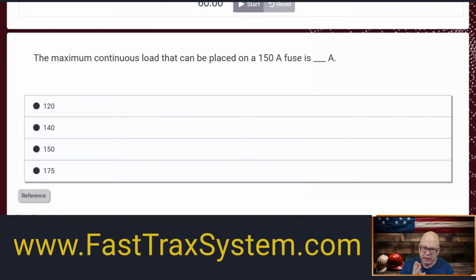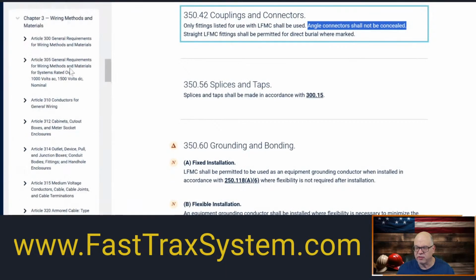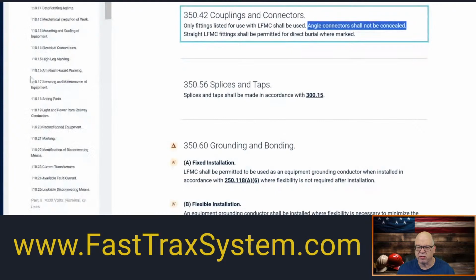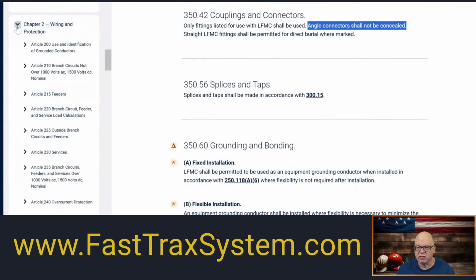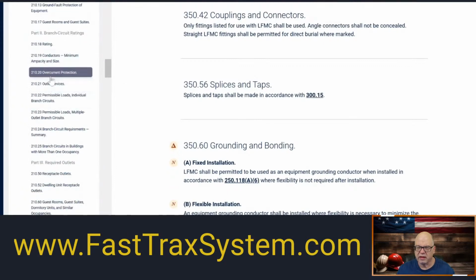So first things first, continuous. The device is rated for 150 amps, and nothing was stated, so it's a fuse. With continuous loads, you're limited to 80%, which is the reciprocal of 125%. So the first thing we want to see is, what is the maximum continuous load that can be placed on this 150? All right, well, let's go to the NEC real quick. Since we're still talking about branch circuit applications, protecting conductors in branch circuit applications, let's go to 210. We were just kind of there. Let's go to 210.20 for overcurrent protection.